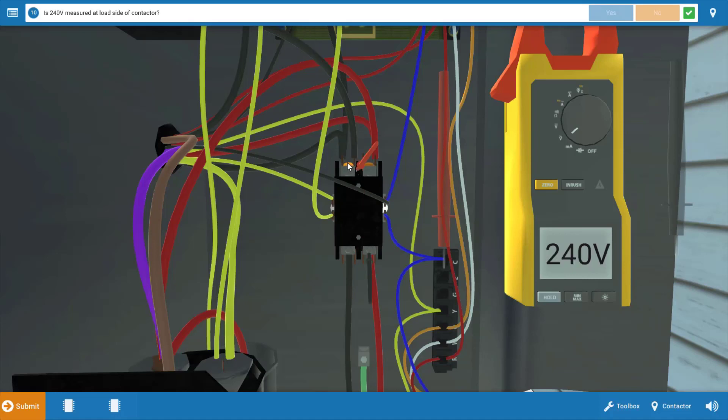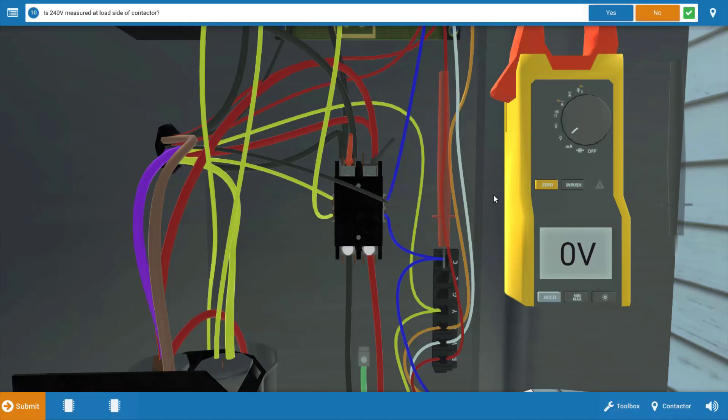Click yes on the procedure guide, and we're going to check the load side voltage now, which is at the top. And this is just going to verify if in fact the contacts closed. So we move our meter leads over here, and when we do that we have zero volts, which means that these contacts are not closing.